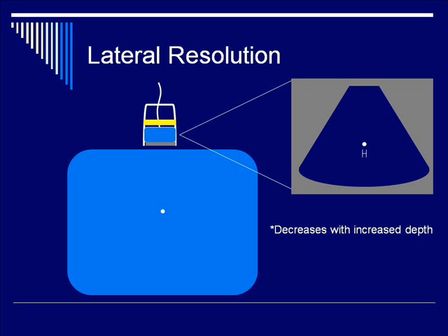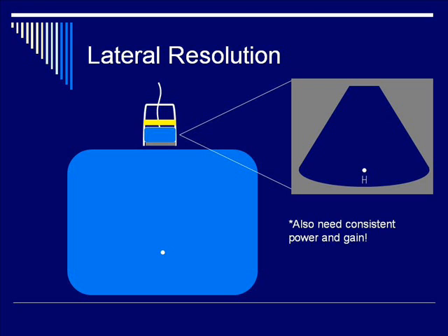Remember that this resolution will decrease with increased depth because the deeper you are, the wider your beam is. So you need to measure this at a variety of different depths. Also recall that because of attenuation as you get deeper into the tissue, this must, must, must be done with consistent power and gain, or your answer will vary from time to time.